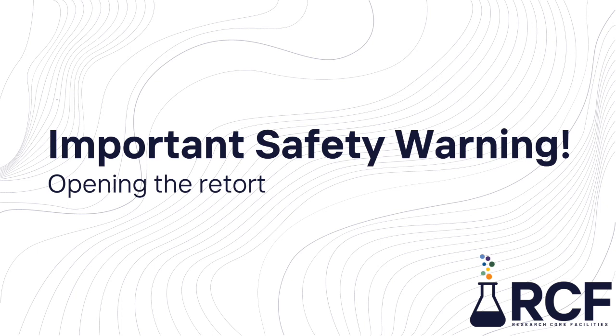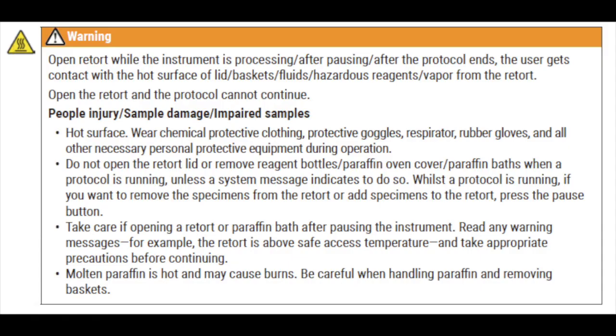Before opening the retort, please be aware of the contents, temperature, and pressure. You must ensure there is no pressure or vacuum inside the retort before you open the lid. You may see a warning if the retort temperature is greater than either the retort empty access temperature or the safe access temperature associated with the reagent in the retort.